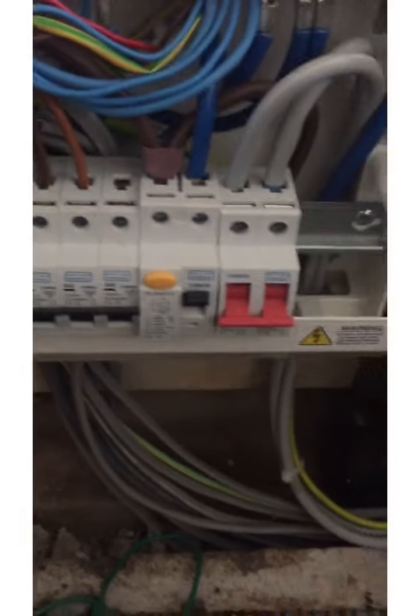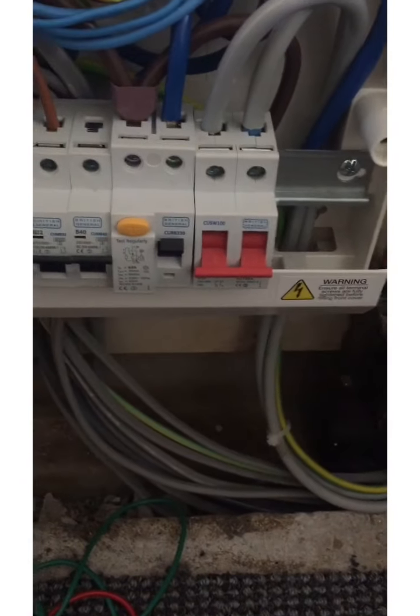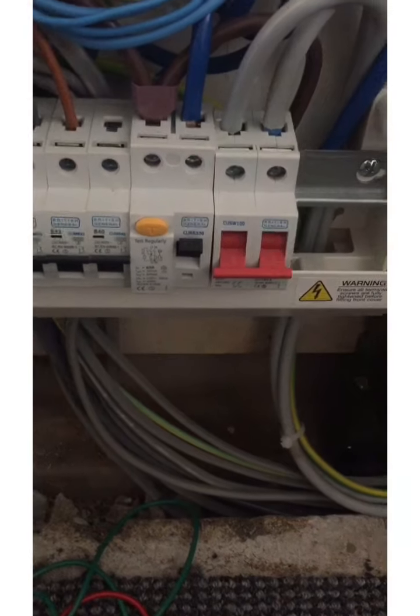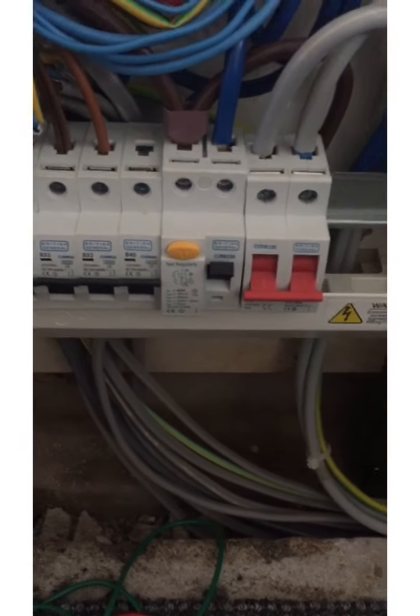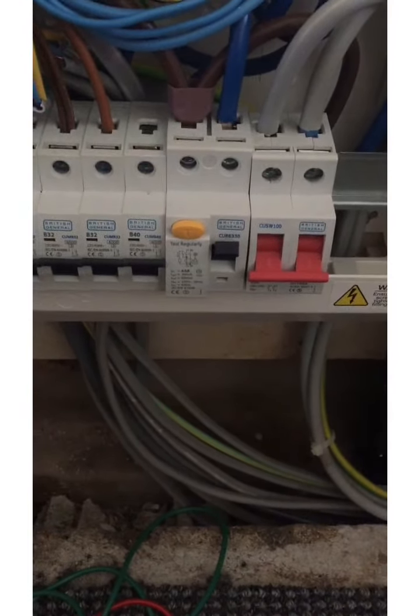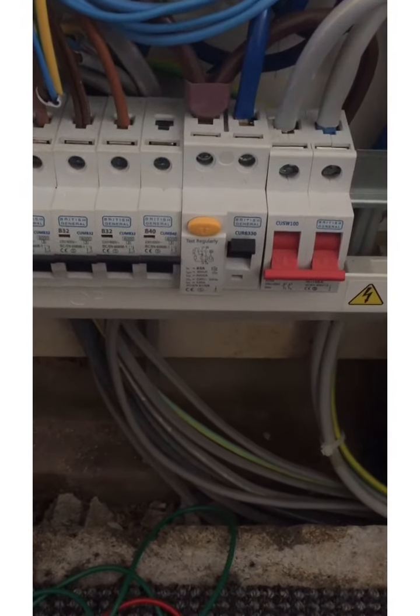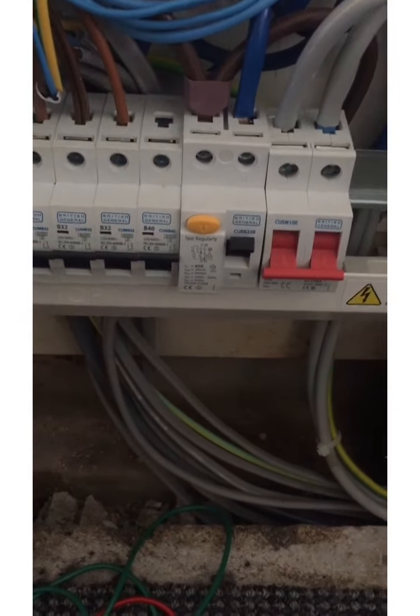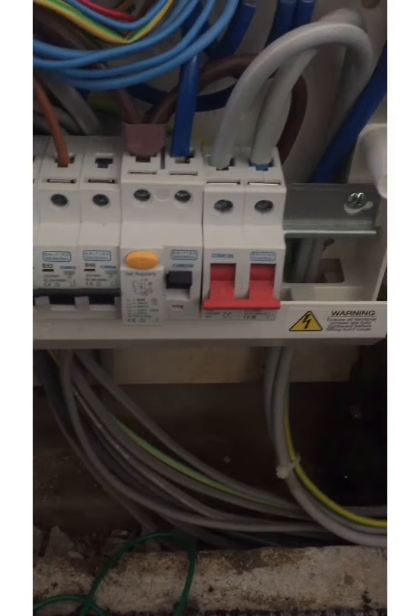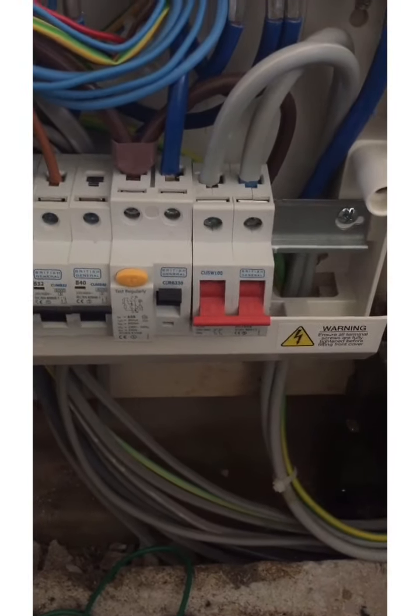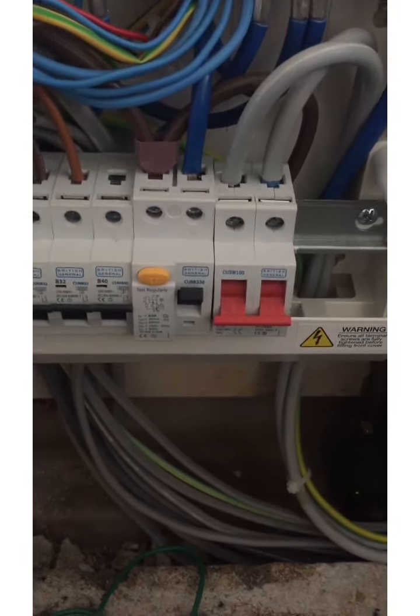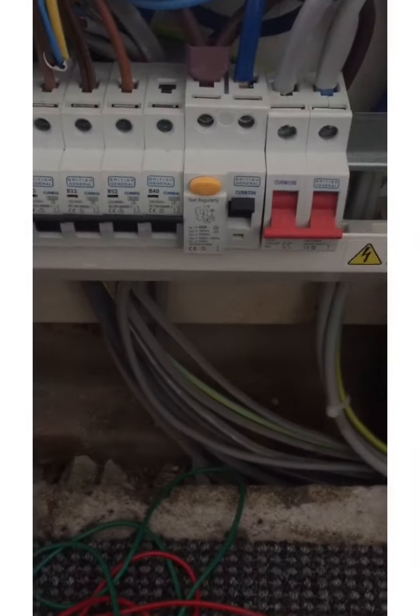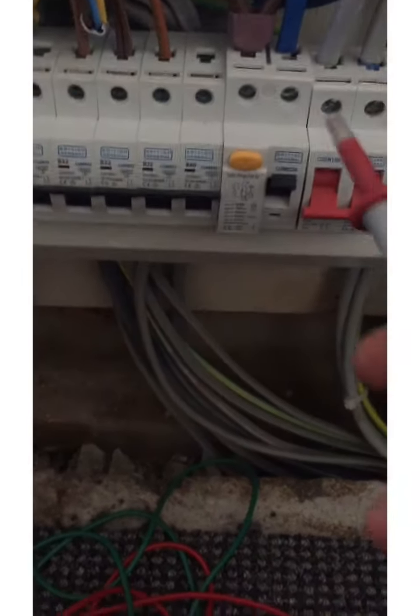Now, this ZE test would have come after a confirmation that the supply polarity is correct. The other thing to say about that is that we get a supply polarity confirmation with every live test that we do in one way or another. But what it recommends in GN3, and I can see why, is that we do the polarity confirmation with a voltage indicator, just because it's clear and unambiguous. We haven't got dials to set up, etc., that we could get wrong. Anyway, enough talking. For now, let's have this.